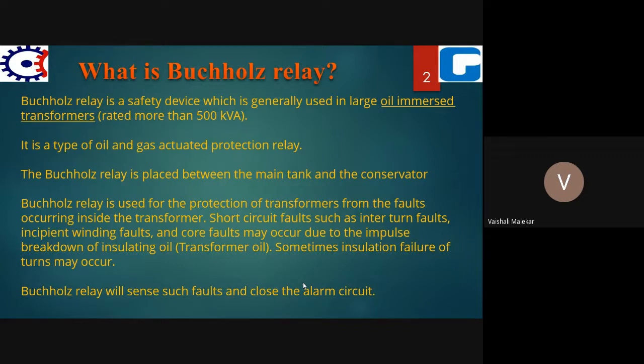So it is an oil and gas actuated protection device. What type of device is it? It is an oil and gas actuated protection relay. Now this relay is placed between the main tank of the transformer, where the oil is filled, and the conservator. There is a pipe connecting the main tank of the transformer with the conservator, and in that pipe this Buchholz relay is placed. It is used for the protection of the transformer from faults which occur inside the transformer.